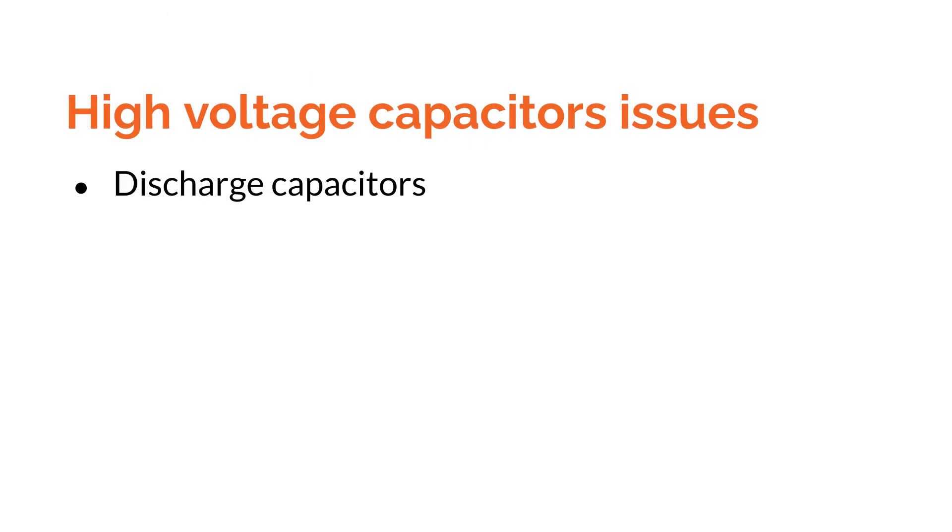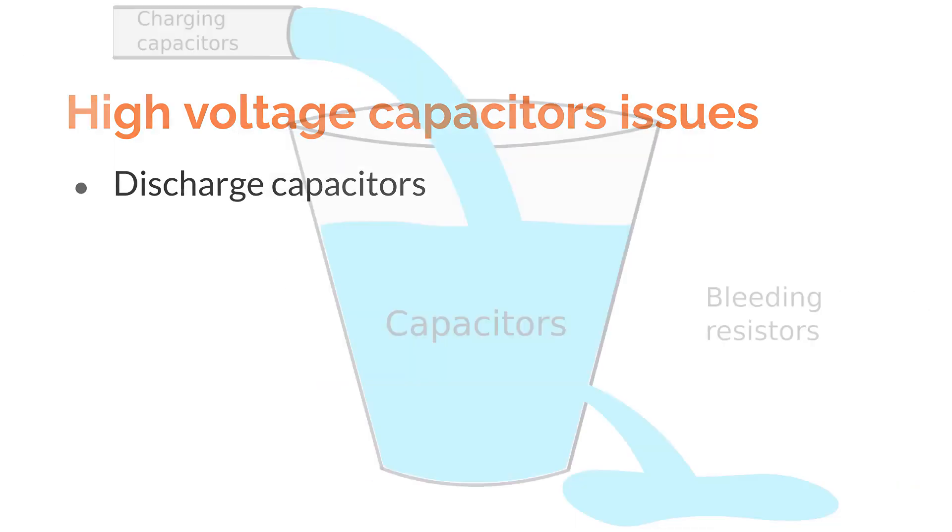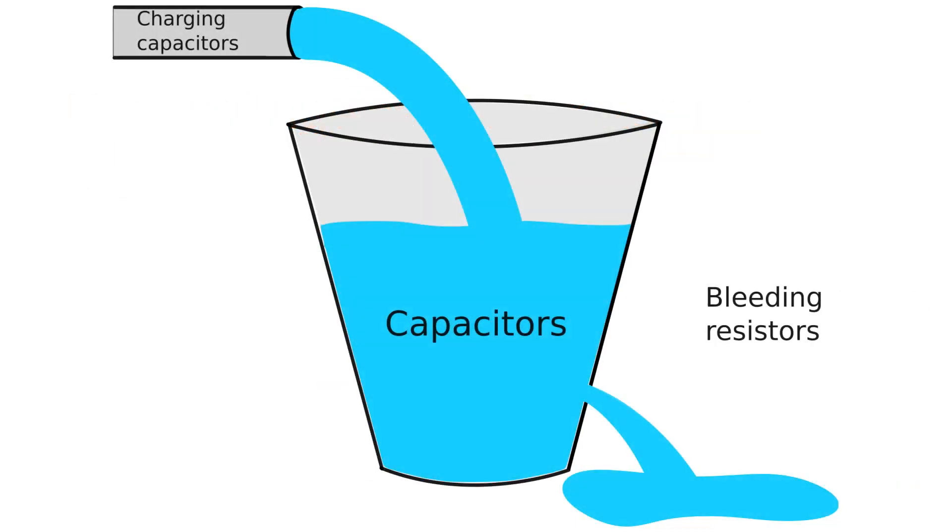Having this much capacitance at a high voltage introduces two new issues. First, I need to discharge the capacitors somehow. I don't want them to hold their charge for a long time after the VFD has been turned off. That's how you accidentally get electrocuted. I want the charge to slowly drain within a few minutes. I can't let it drain too quickly, however, otherwise it'll be much harder to charge the capacitors when I am using them.